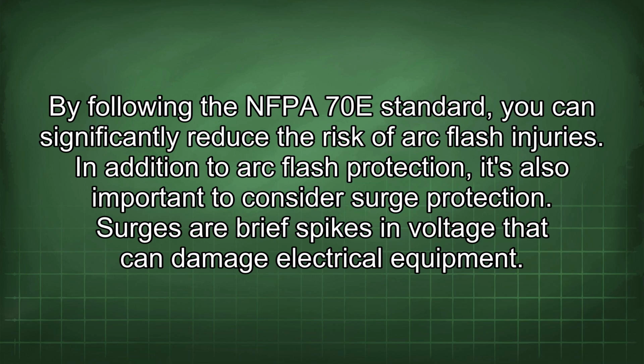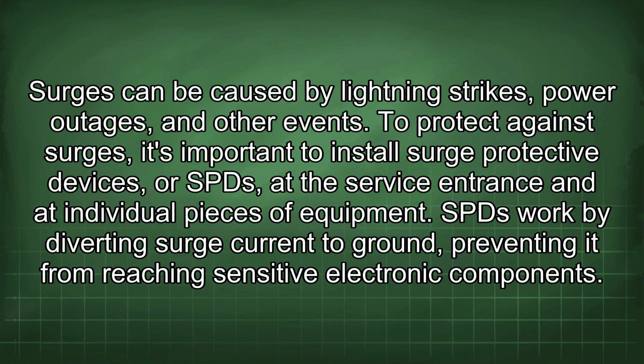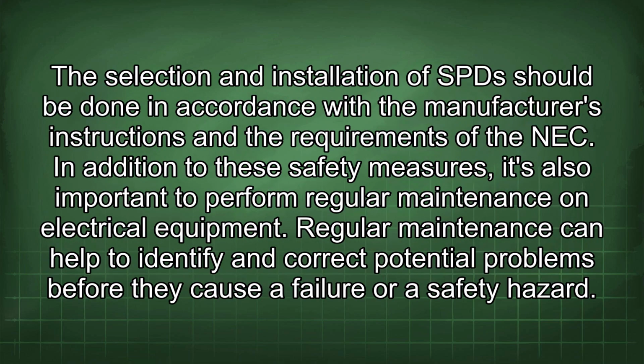In addition to arc flash protection, it's also important to consider surge protection. Surges are brief spikes in voltage that can damage electrical equipment. Surges can be caused by lightning strikes, power outages, and other events. To protect against surges, it's important to install surge protective devices, or SPDs, at the service entrance and at individual pieces of equipment. SPDs work by diverting surge current to ground, preventing it from reaching sensitive electronic components. The selection and installation of SPDs should be done in accordance with the manufacturer's instructions and the requirements of the NEC.